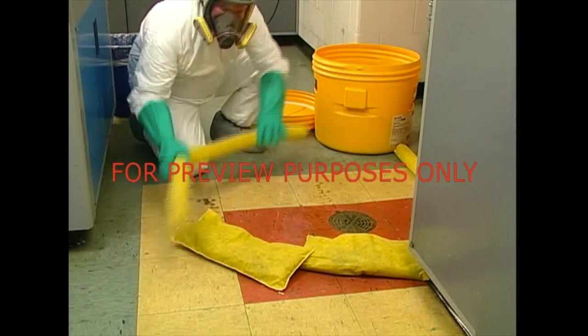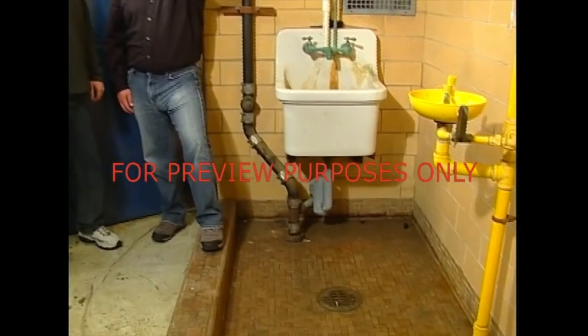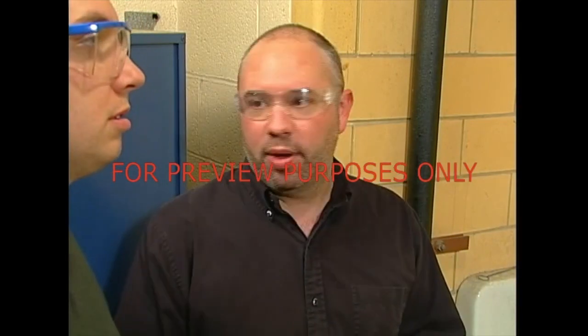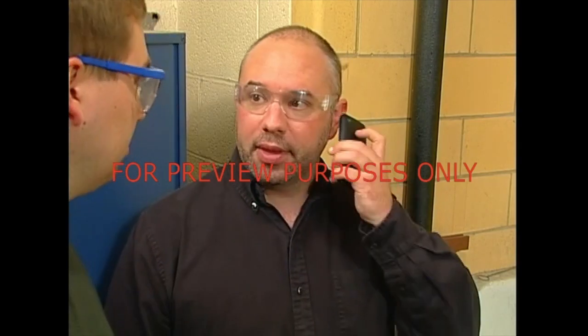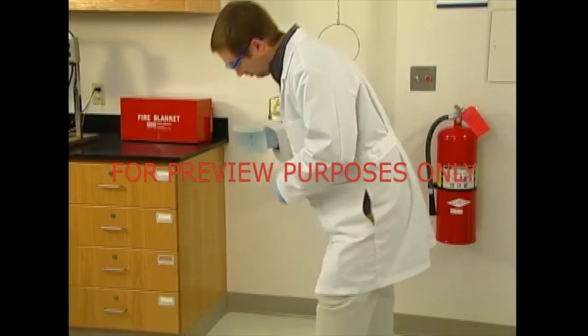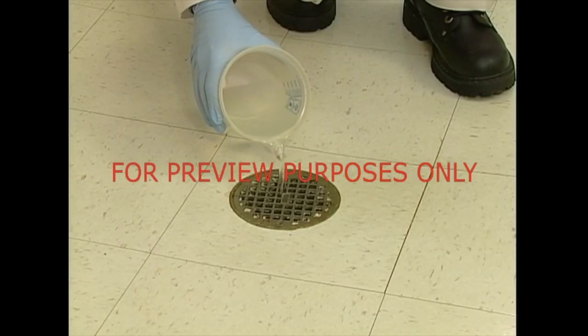Disposal of the shower water can often be an issue. In some situations, the water will need to be disposed of as chemical waste. This is especially true if the spilled substance is radioactive. Stripped-off clothing should be decontaminated prior to normal laundering. If the spilled substance is particularly hazardous, the clothing should be disposed of. If there's a drain under the shower, you must know whether it empties into a storage tank or the sewer. If it's the sewer, your supervisor may need to alert outside agencies. And remember, if a shower does have a drain, water should be kept in the trap at all times. This will keep sewer gases from seeping up into the room. These gases can be both flammable and toxic.